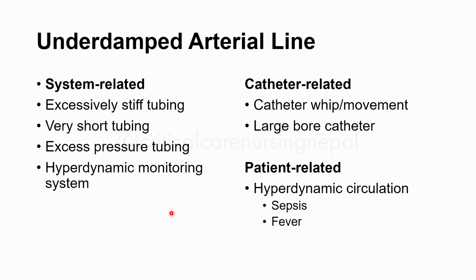It could be related to the system, the catheter, or the patient, but for most things you always need to see the patient first before checking all other things, right? So here we see the causes for the underdamped arterial line. In system related causes, it could be due to excessively stiff tubing. Of course the tubing needs to be non-compliant, but if it is very stiff, then it could lead to more than 3 oscillations, and it is called underdamped.